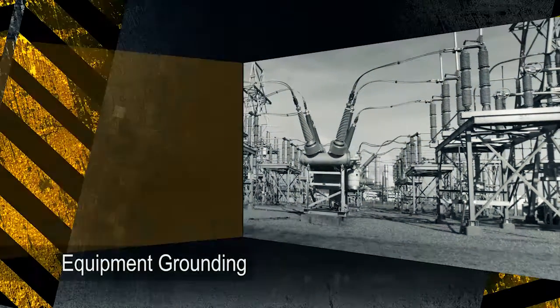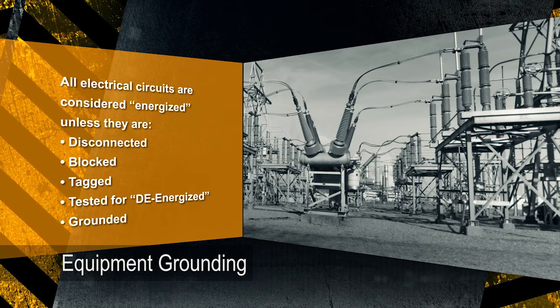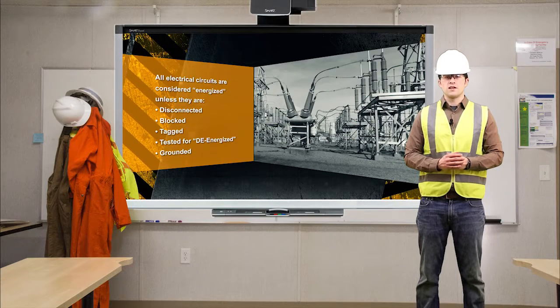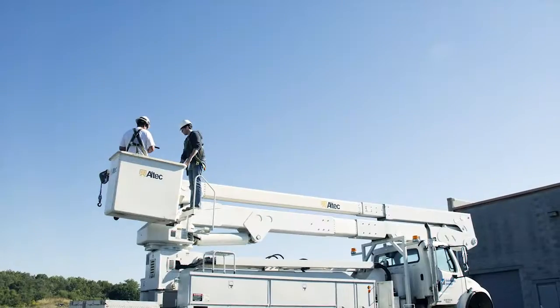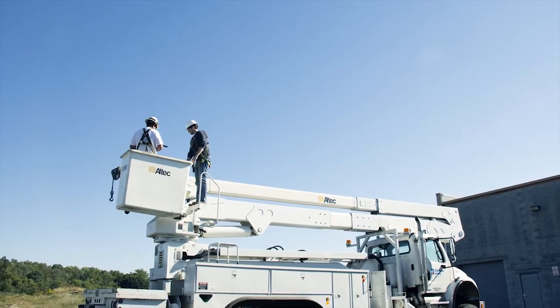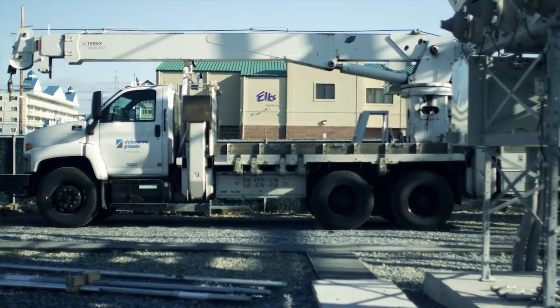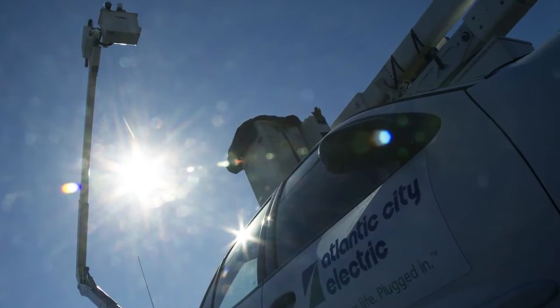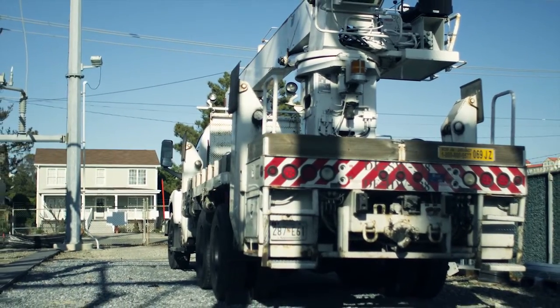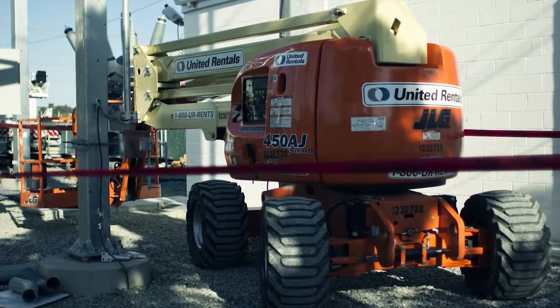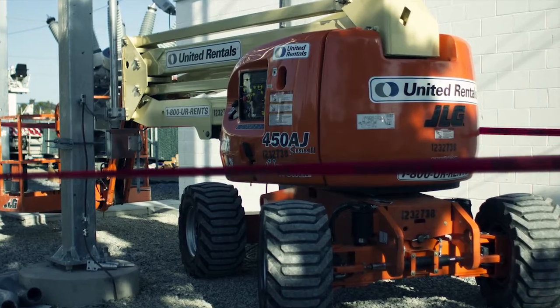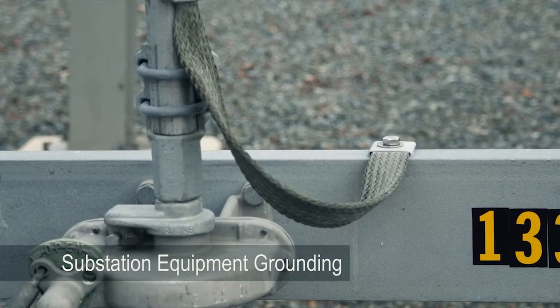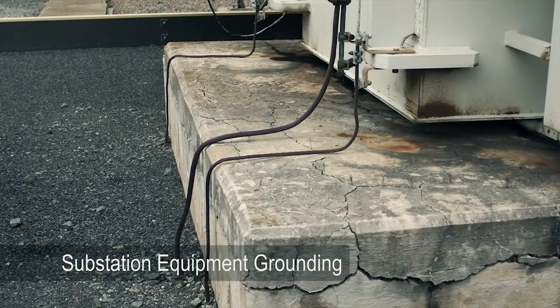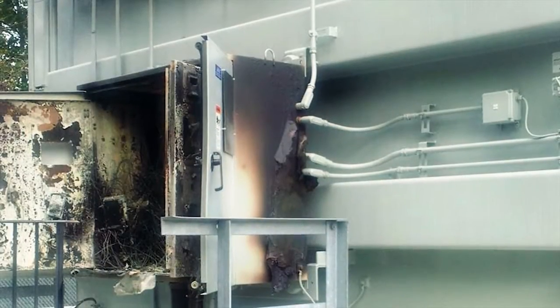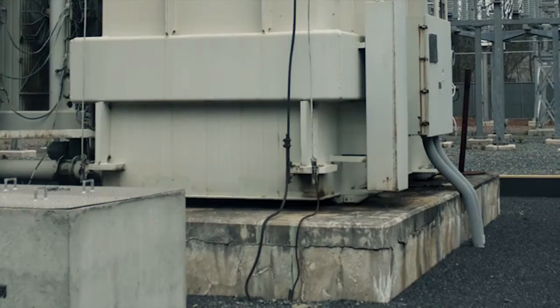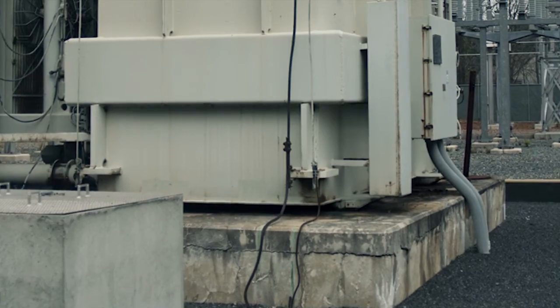All electrical circuits are considered energized unless they are disconnected, blocked, tagged, tested for de-energized, and grounded. Vehicles and equipment used to conduct work in an energized zone of the substation yard, e.g. bucket trucks, digger derricks, cranes, etc., shall be grounded when working in substations and substation yards. Proper grounding is required for all vehicles and equipment operating in energized zones and meeting the minimum grounding requirements. Verify any substation equipment you must perform work on or near is properly grounded. Missing groundings can result in failure of equipment as well as injury. Always remember, if it is not grounded, consider it energized.